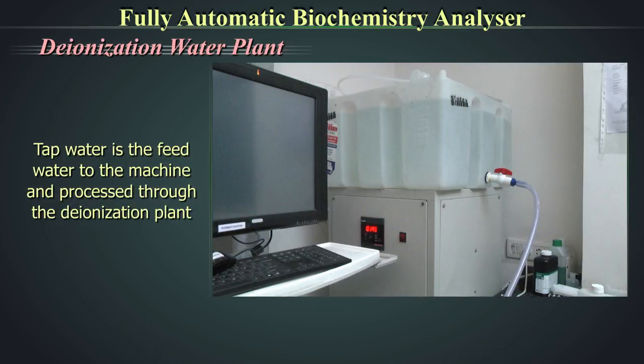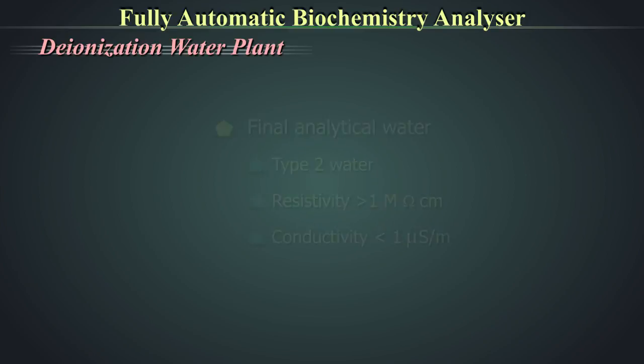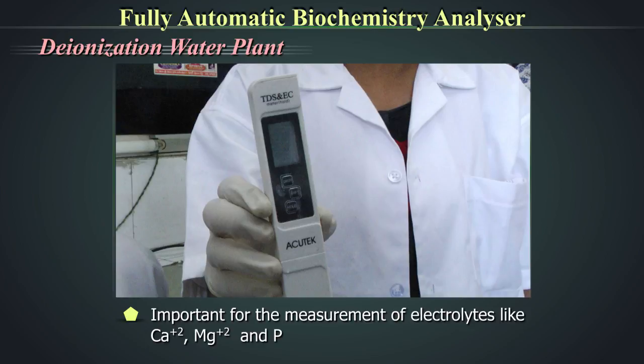The deionization water plant processes tap water as feed water. The final analytical water is Type 2 water with resistivity more than 1 and conductivity less than 1 microsiemen per centimeter as per the American Society for Testing and Materials. These two parameters should be checked daily and documented. If using commercially purchased deionized water, conductivity and resistivity can be checked by a handheld device. This is very important for the measurement of certain electrolytes like calcium, magnesium, and phosphorus.